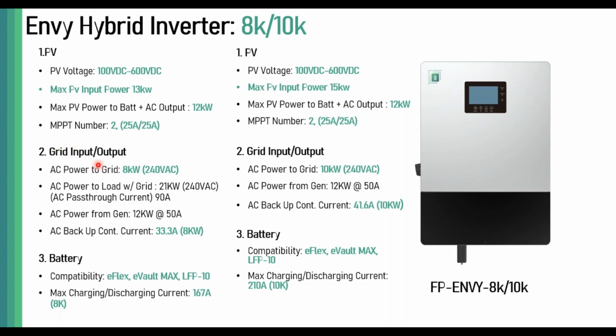The max MPPT current is 25 amps. It has two MPPT ports, right, where you can connect up to 4 strings as well. Each string is about 15 amps. Yes, about 15 amps. This 8K and 10K can tolerate up to 25 amps per MPPT.